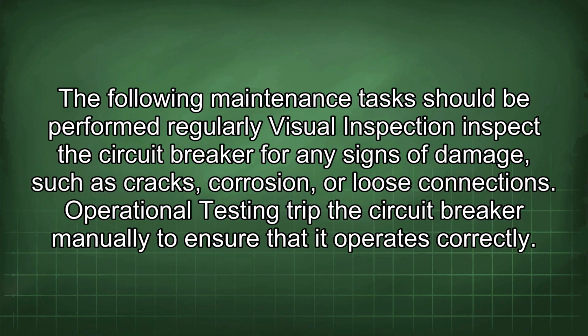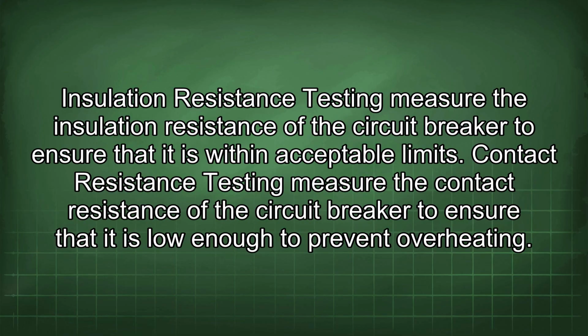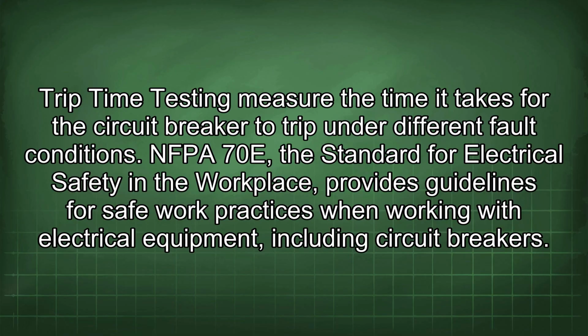The following maintenance tasks should be performed regularly. Visual inspection. Inspect the circuit breaker for any signs of damage such as cracks, corrosion, or loose connections. Operational testing. Trip the circuit breaker manually to ensure that it operates correctly. Insulation resistance testing. Measure the insulation resistance of the circuit breaker to ensure that it is within acceptable limits. Contact resistance testing. Measure the contact resistance of the circuit breaker to ensure that it is low enough to prevent overheating. Trip time testing. Measure the time it takes for the circuit breaker to trip under different fault conditions.